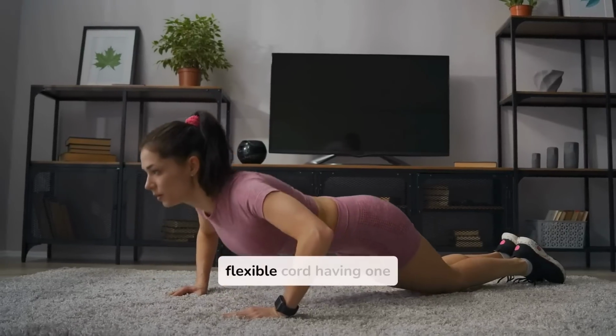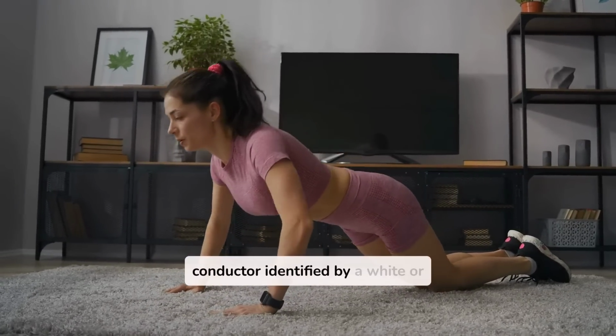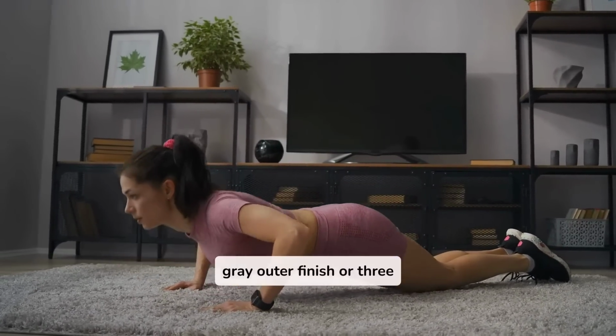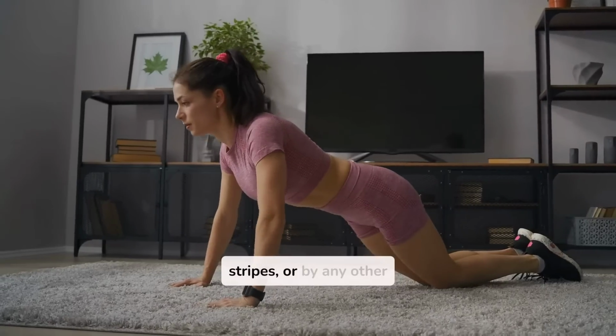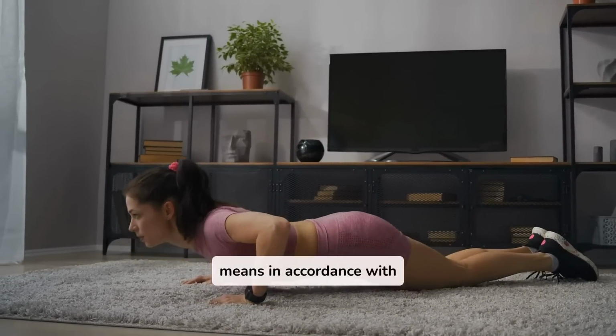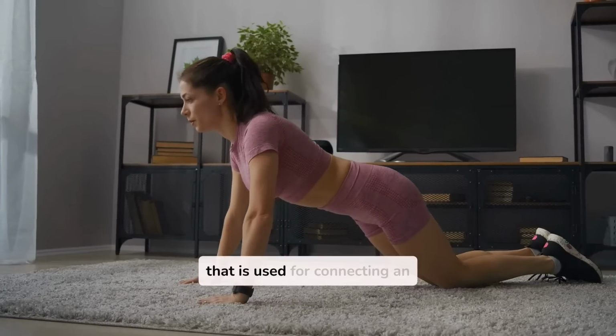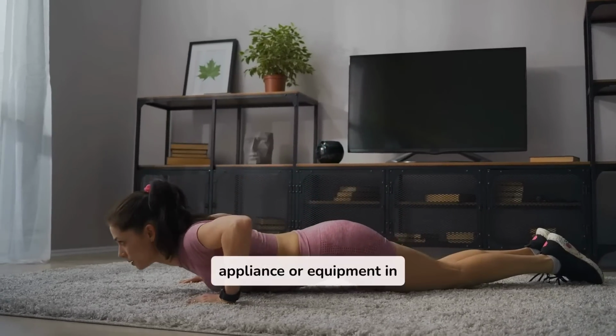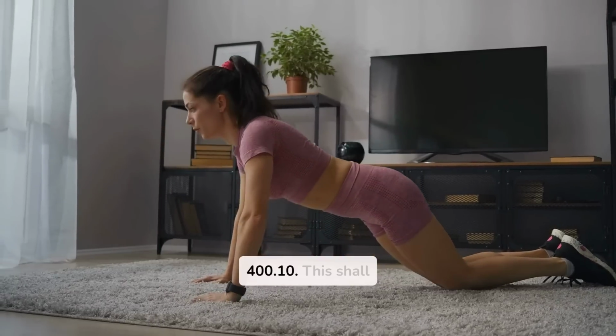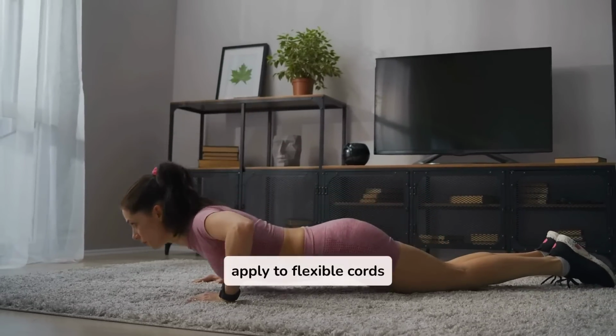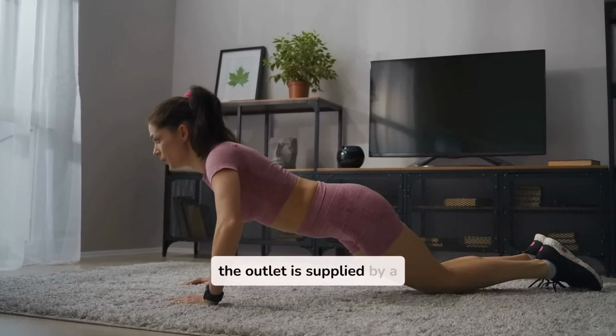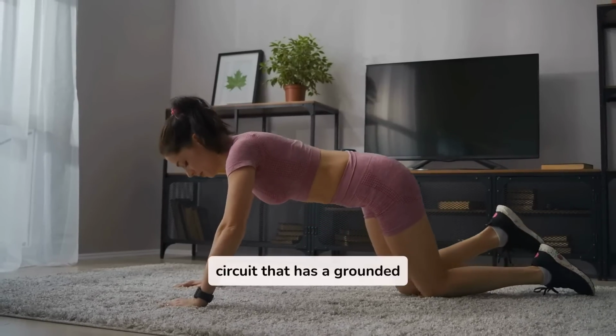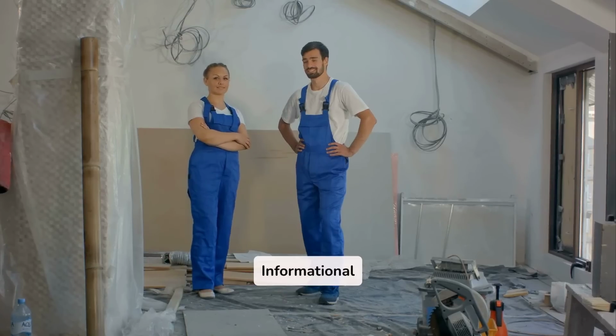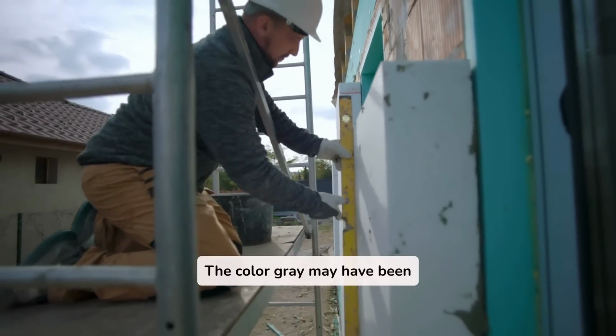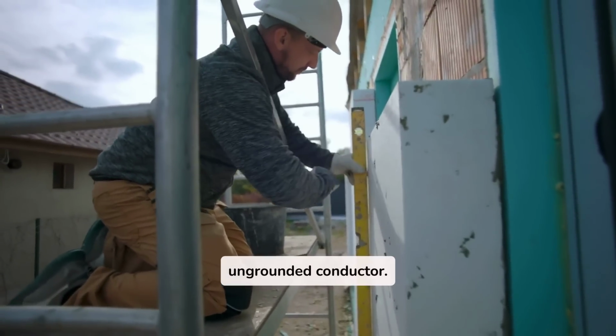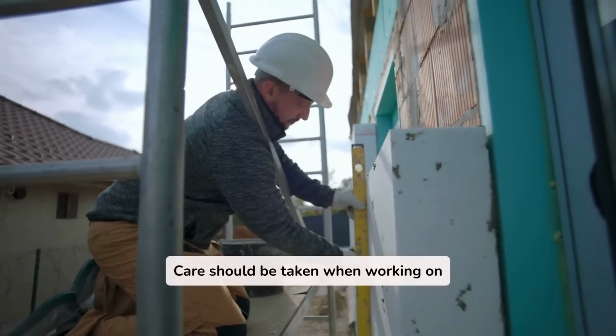2. A flexible cord having one conductor identified by a white or gray outer finish or three continuous white or gray stripes, or by any other means in accordance with 400.22, that is used for connecting an appliance or equipment in accordance with 400.10. This shall apply to flexible cords connected to outlets whether or not the outlet is supplied by a circuit that has a grounded conductor. Informational note: The color gray may have been used in the past as an ungrounded conductor. Care should be taken when working on existing systems.